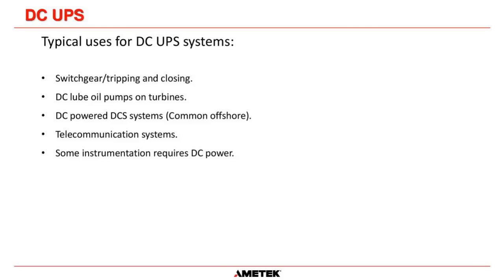You also find that, especially on offshore platforms, you will have DC-powered DCS systems. Now, in most petrochemical plants and onshore facilities, they usually use an AC UPS that then powers the AC to DC converter in the DCS system. But offshore, there are DCS systems that are designed for 24 volts or 48 volts DC.